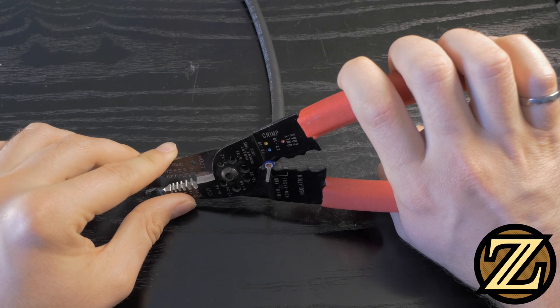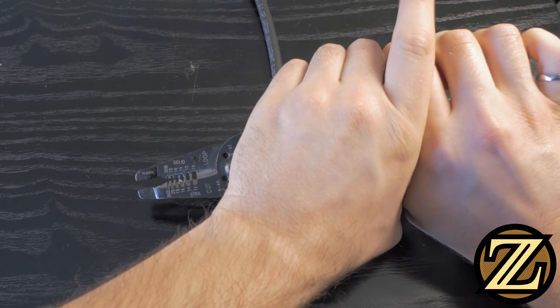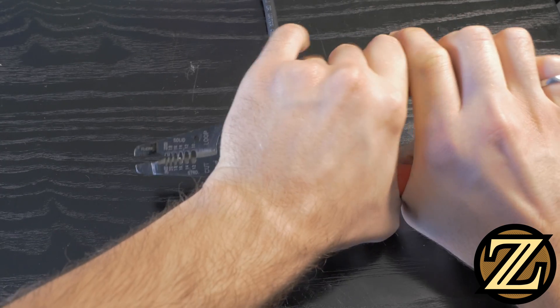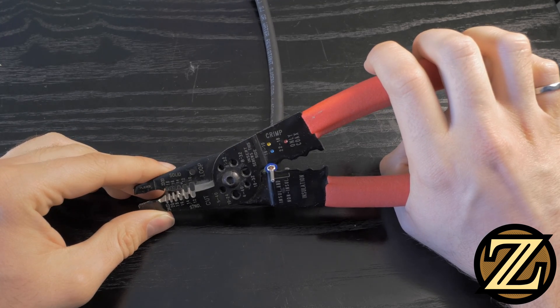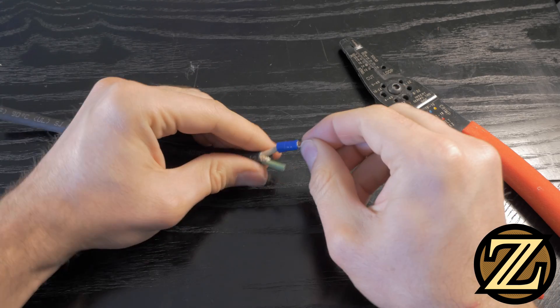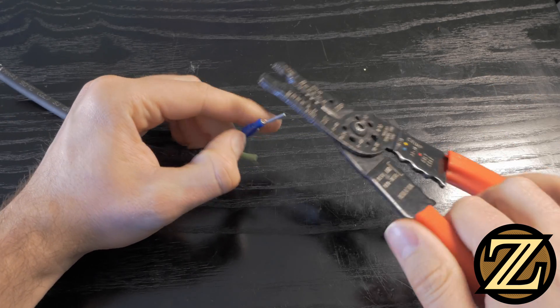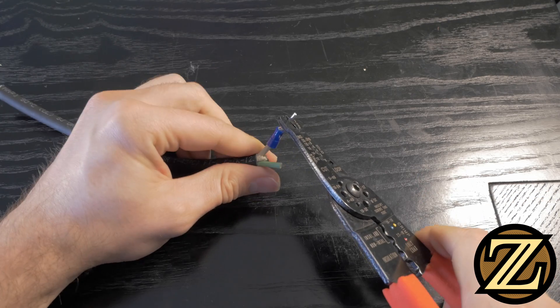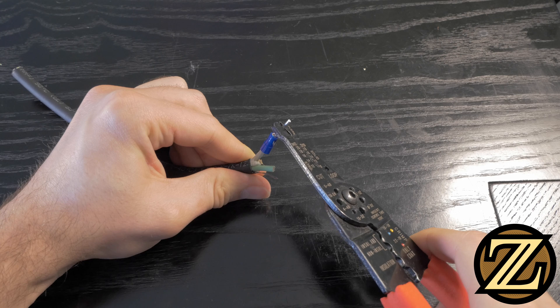When you're all set up, squeeze and squeeze hard. If you require two hands to get the leverage because you're filming a video like this and it's awkward, that's okay, as long as you can squeeze hard enough to actually get the crimp job done. When you're done, you should not be able to remove the terminal off the end of your wire. You can even take your pair of pliers and try and pull it. And if you can't remove it, then you know you've done the job correctly.